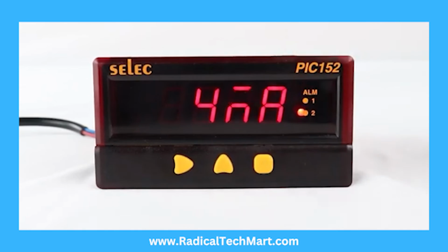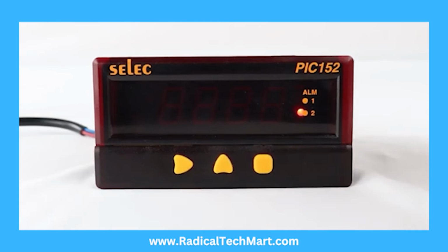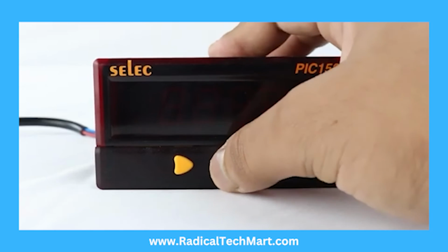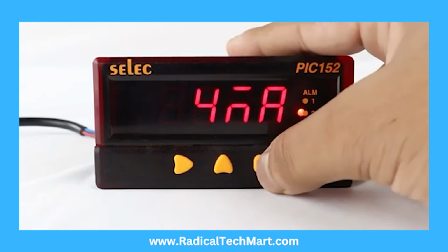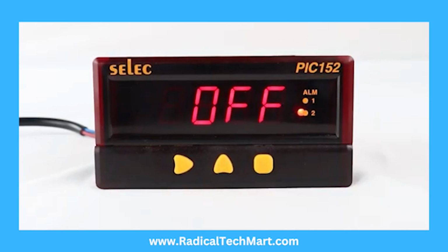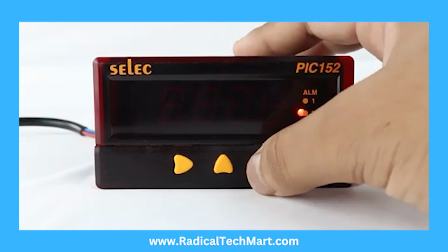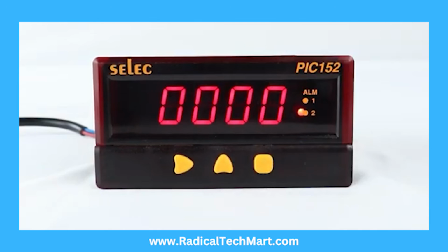Press the square key to select analog output type, which can be selected as 4 to 20 mA, 0 to 10 volt, 0 to 5 volt, 0 to 20 mA, by pressing the up arrow key. Next, press the square key to use manual output. Can set low scaling point, ALO, as 0 for retransmission, if input is thermocouple and retransmission output 0 to 20 mA.